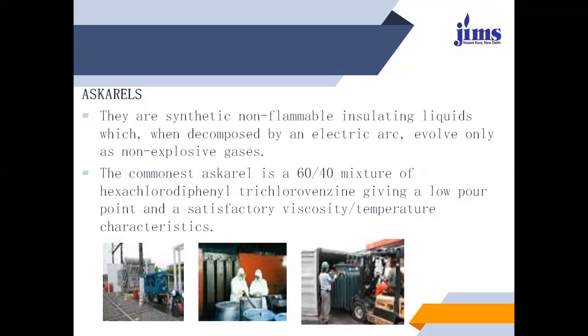The dominant askarel is a 60 or 40 mixture of hexachlorodiphenyl and trichlorobenzene, giving a low pour point and a satisfactory viscosity-temperature characteristic. This combination is better because whenever it is decomposed by electric arc, it never develops explosive gases.